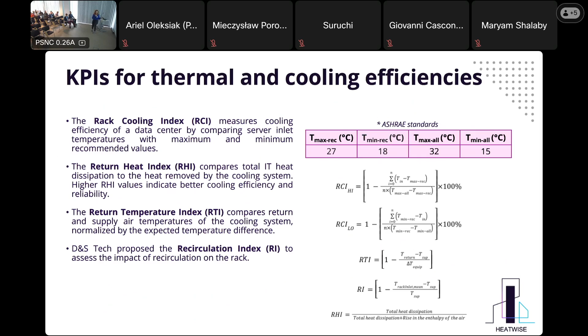And as D&S Tech, we proposed one more index, the recirculation index, to assess the impact of recirculation on the rack. Hot air dissipates from the server and then may come back, and we have to address how it's measurable. We measure this with the recirculation index. And this is the table of target and allowable ranges of KPIs, and this is the original layout of the PSNC and Aalborg University's KPIs.